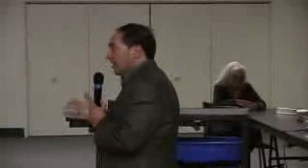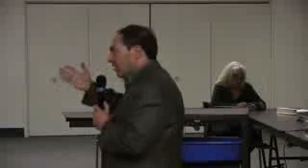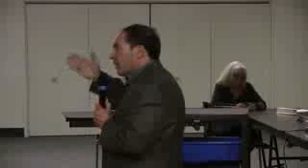But I'll tell you what. An error was made in Arizona. That should not have caused the whole grid to come down from Arizona to Mexico up to Orange County. It shouldn't have happened, period. And when I was answering this gentleman's question regarding how much reserve we have this summer, the system is designed so that if you lose your largest transmission line and your largest single generator, you shouldn't lose one customer, not one. There's still a FERC study being done. I know it's been quite a while since September 8th, but FERC and each of the utilities involved and some other agencies are looking millisecond by millisecond at what happened, because we have all that instrumentation.